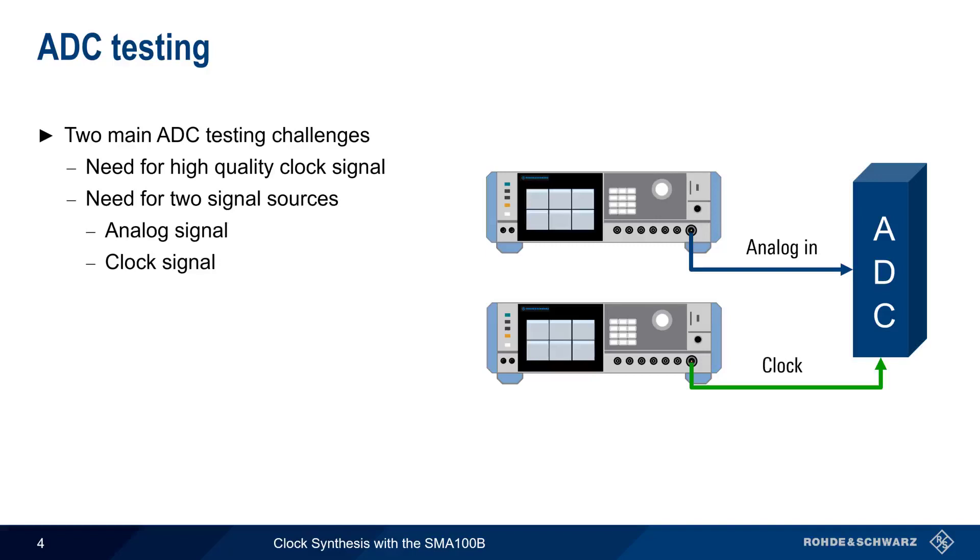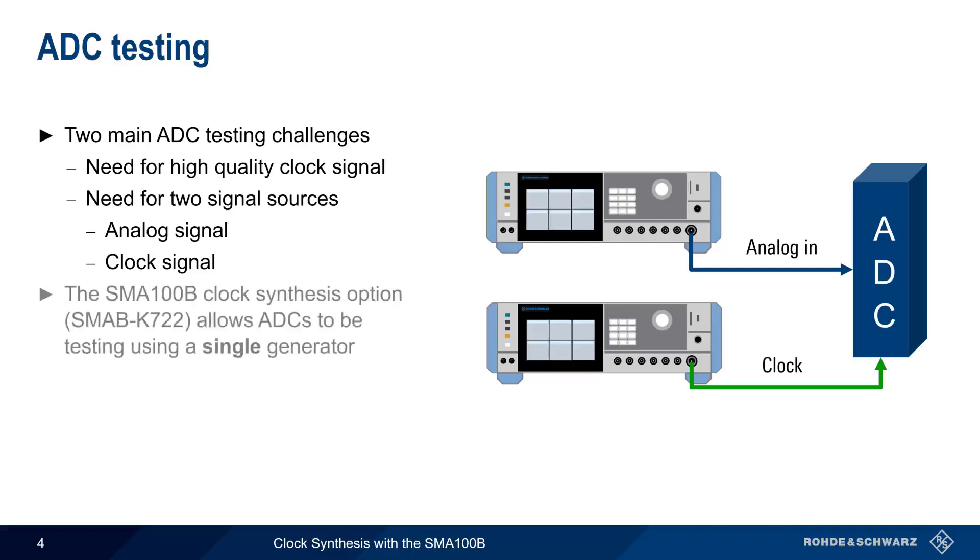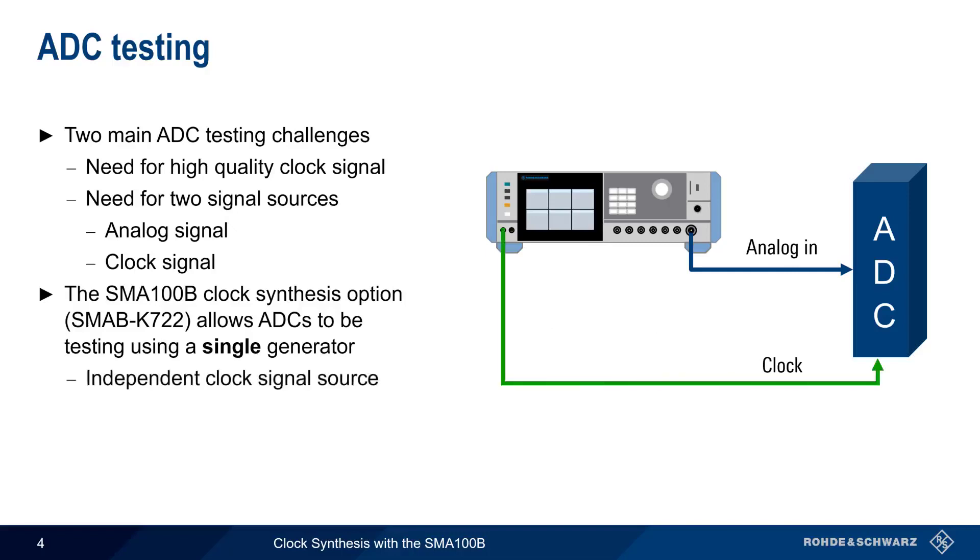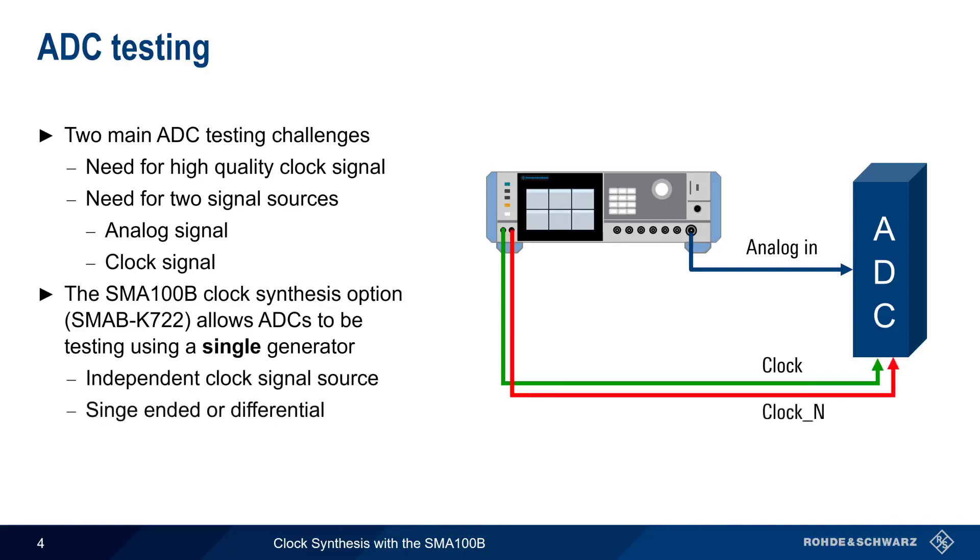On the SMA100B, the clock synthesis option allows ADCs to be tested using only a single signal generator. In addition to the analog in, an SMA equipped with a clock synthesis option can also provide a completely independent, high-quality clock signal, either as a single-ended or as a differential signal.